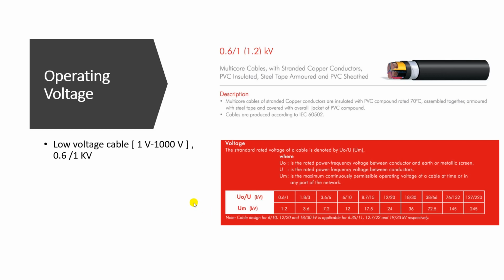So how can we know if it is a low voltage, high voltage, or medium? The low voltage cable is a cable which operates in voltage between 1 volt to 1000 volt, or 1 kilovolt. The maximum line-to-line voltage at which it will operate is 1 kilovolt. So if we are working in a network which has a voltage less than 1000 volt, then it is a low voltage network, and we will use a low voltage cable.